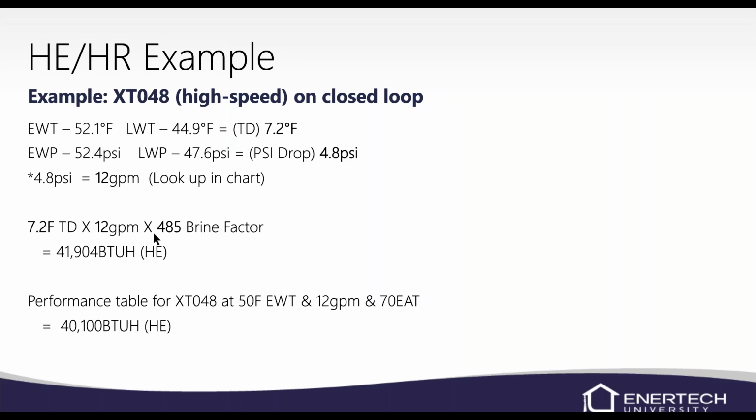I'm going to tell you we have antifreeze in the system because it's a closed loop, so our brine factor is 485. If we do the math on that, it's 41,904 BTUs. And really that's just a number until we compare it to the IOM.